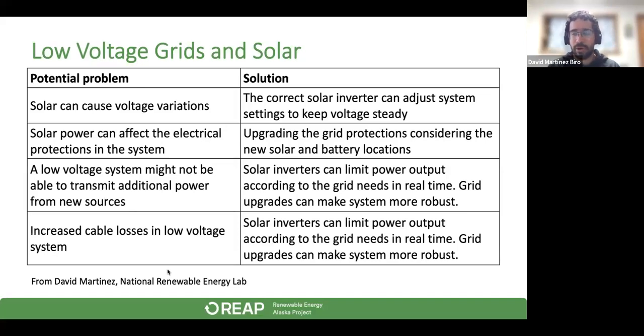It's not totally required, so you could only have PV with very good controls that limit the amount of PV going into the grid, and also the amount of generation the diesel genset is generating. So you can choose, but in this case I would say the best option for McGrath is also to consider batteries to have the additional benefits in the grid.